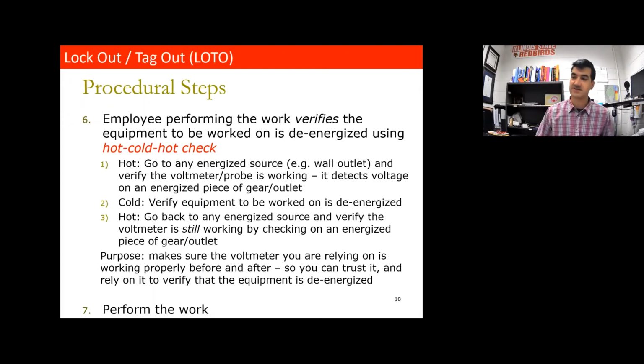The third step is making sure that multimeter is still working properly. So you take your multimeter, go back to some other energized source, and check that it's still working. It measures 120 volts AC, or whatever it should be. So you're taking your multimeter, checking that it works on some other energized piece of equipment. Then go to the de-energized equipment you're going to work on, check that it's de-energized. Then take your multimeter and go back to some other piece of equipment, electrical outlet or whatever, and check that it works.